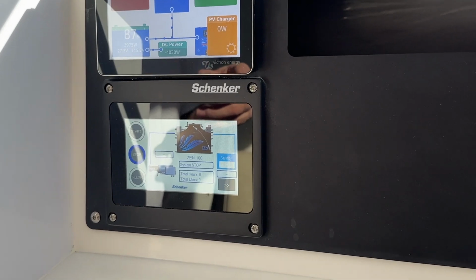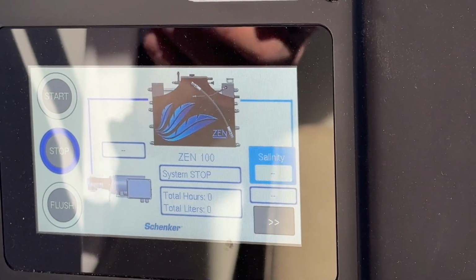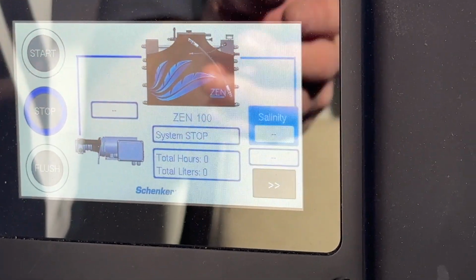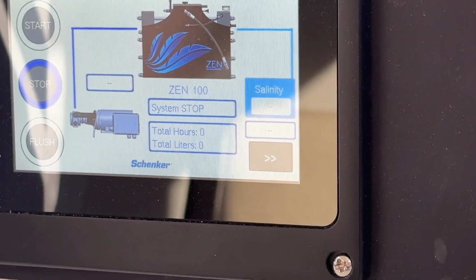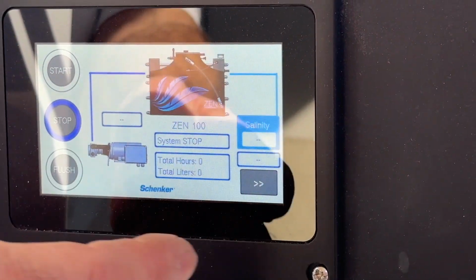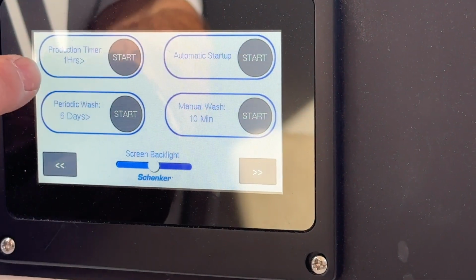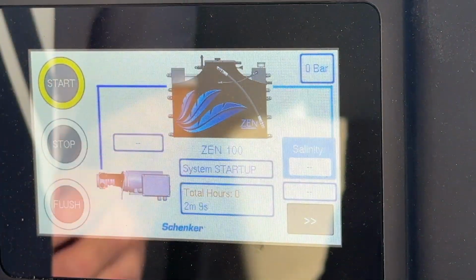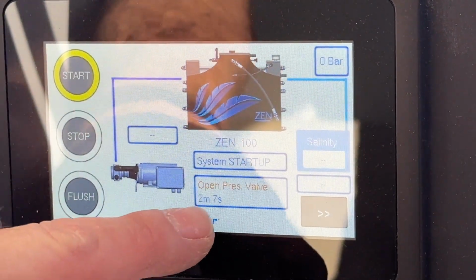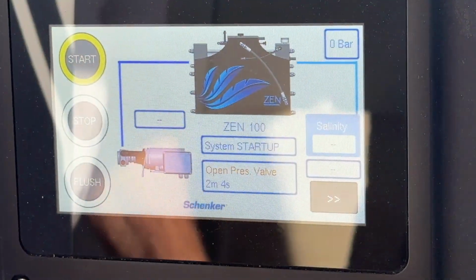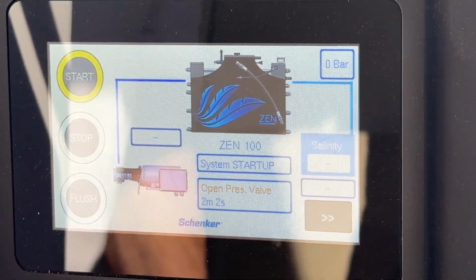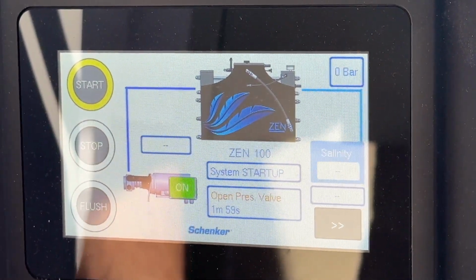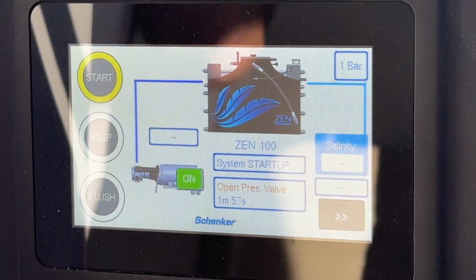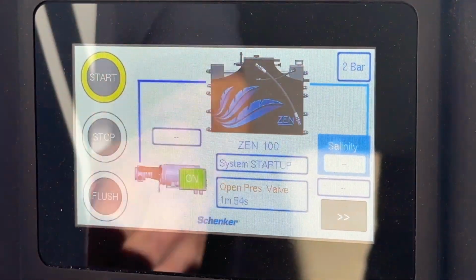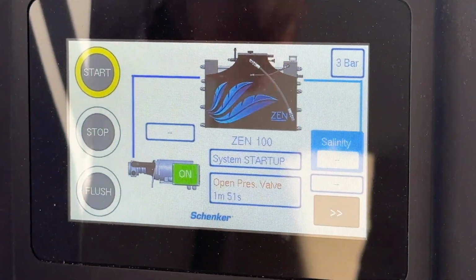So the procedure to start it up whenever you introduce air in the system is what we call the startup procedure. And this uses a combination of your pressurized freshwater system to feed the system of air. Production timer, automatic startup. So we'll start that now, with the open pressure valve. That's the decompression valve on top of the unit. I did leave it open, so I'm not going to worry to go and open it now. So this lasts for just under 2 minutes, and with about 50 seconds remaining it will prompt us to go and close the decompression valve.